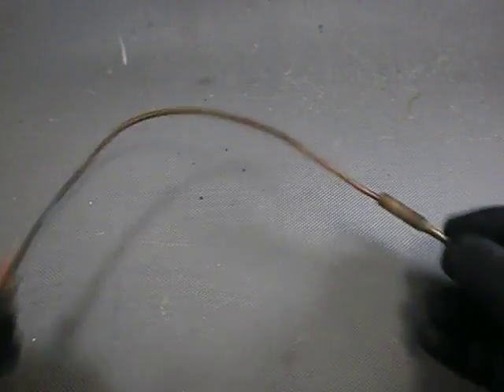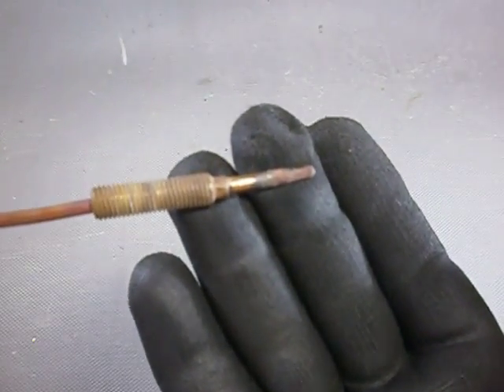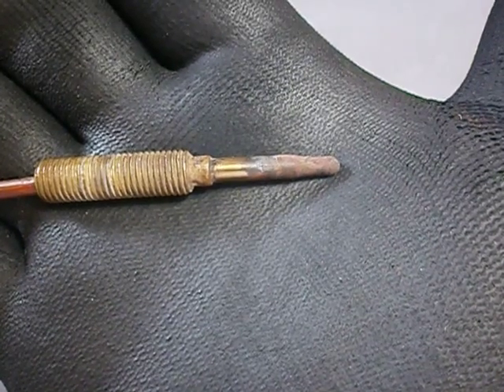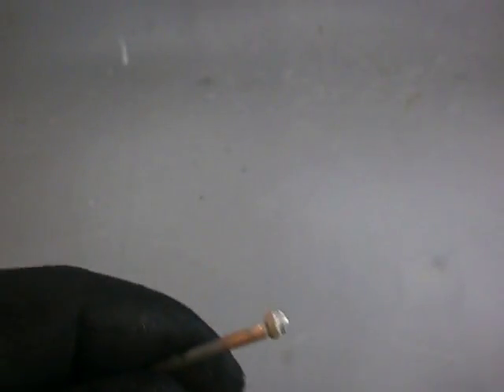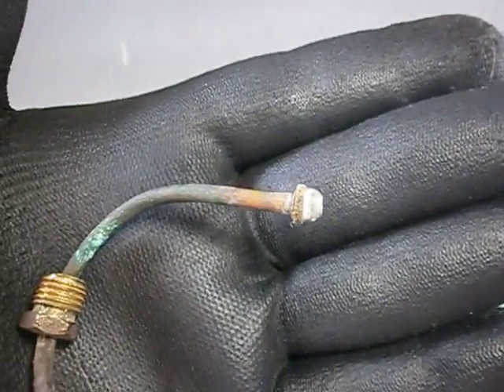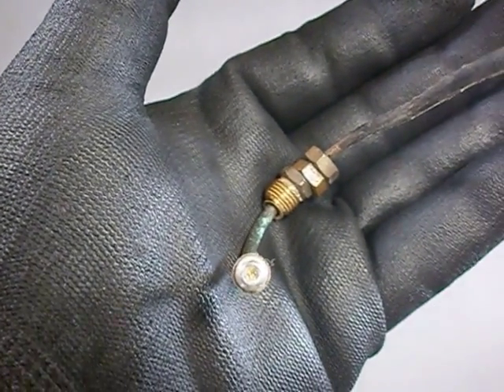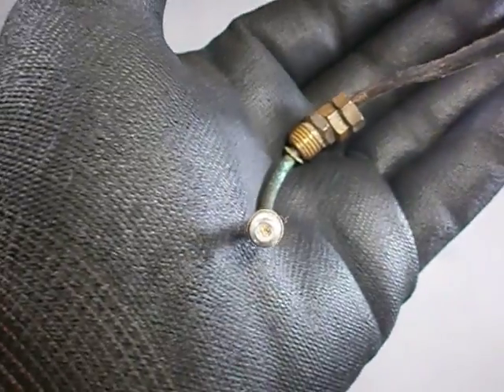So I decided to remove it and inspect it. We can see that our specimen here is pretty crusty. Its conductors are protected by a copper tube and here we have its connector for the cold junction, which is also very much affected by corrosion. My suspicion falls on the poor contact of the cold junction. I will remove this crud and return in a moment.